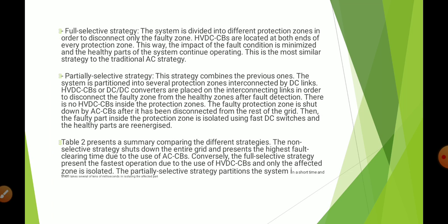Full selective strategy. The system is divided into different protection zones in order to disconnect only the faulty zones. See, if there are three zones, we can disconnect only the faulty zone and the others keep working regularly. HVDC circuit breakers are located at both ends of every protection zone. Like there will be a circuit breaker at the start of the first and the end of the first, at the start and end of the second, and at the start and end of the third. Like this, there will be circuit breakers at both ends of each zone. This way, the impact of the fault condition is minimized and healthy zones continue operating. This is the most similar strategy to the traditional AC strategy we have used for years.